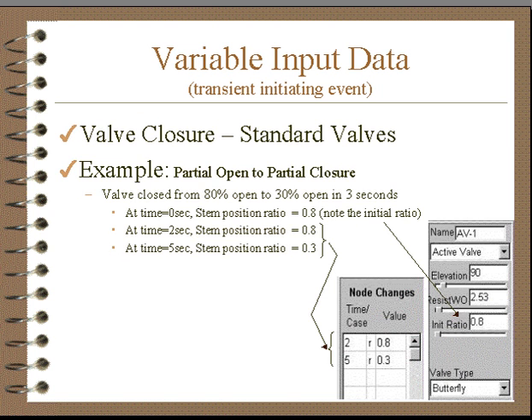With standard valves, we don't have to go from fully open to fully shut. This illustrates one where at two seconds it's 80% open, which means the stem has only moved 20% of its position. At time five, it's only 30% open, and this would be a butterfly valve. The program will calculate the effective areas for this type of valve.